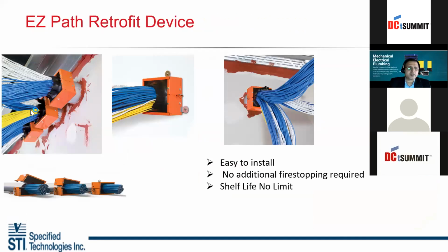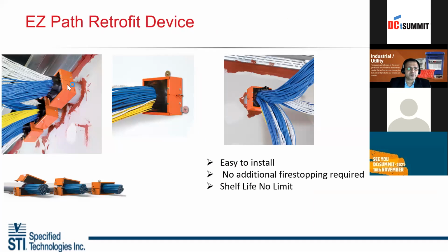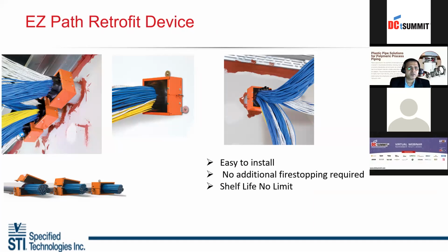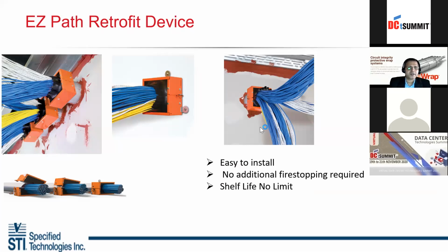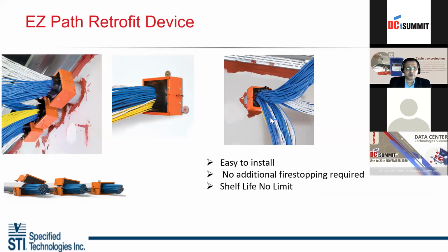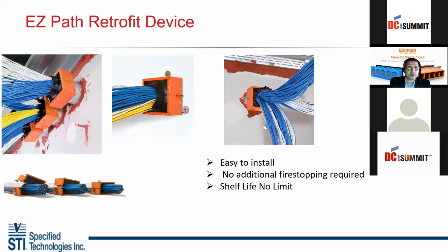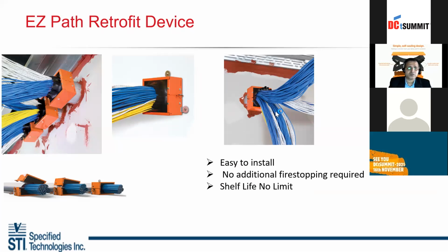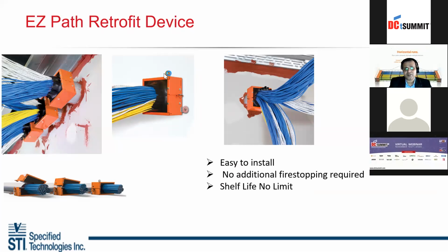Retrofit, I think I already explained, but I was just trying to explain with 3 different pictures, where you have 3 different sleeves with 100% cables. See how easily it is installed, and the fire stopping is the correct one. So no additional fire stopping is required in this. In other scenarios, you have the sealants, putties, and other things to be installed. Here, you don't have any additional product to be installed. This itself will act as a cable pulling device as well as a fire stopping device.